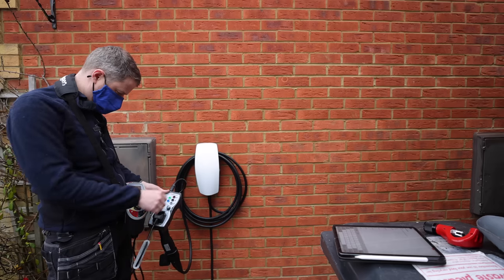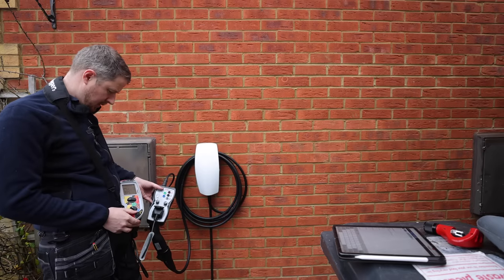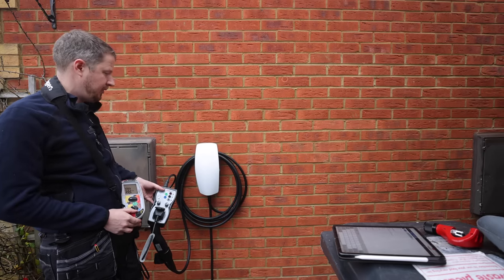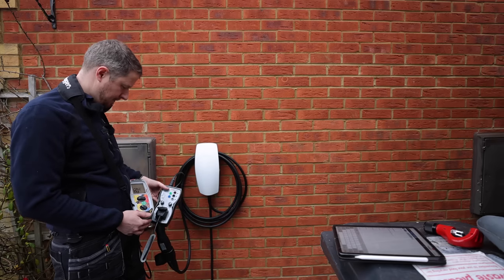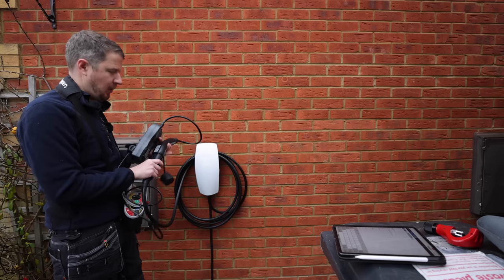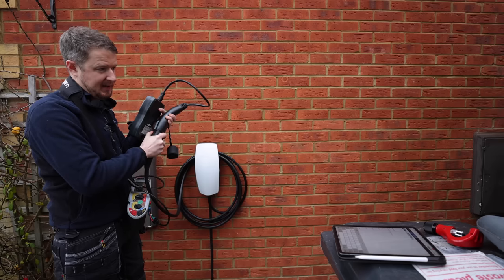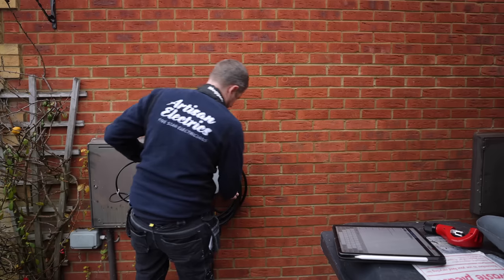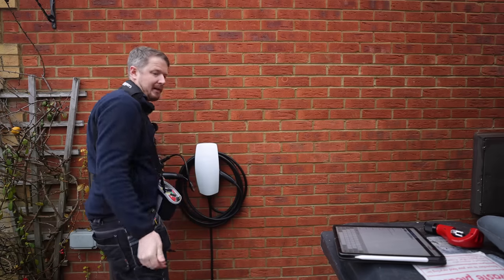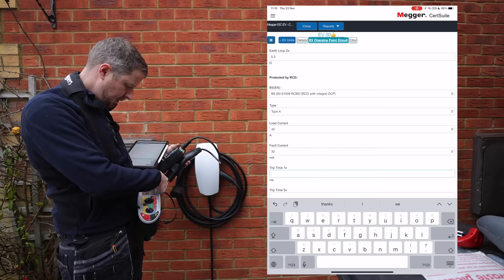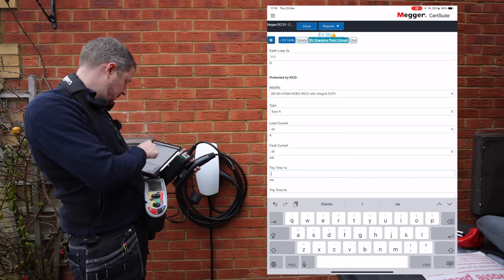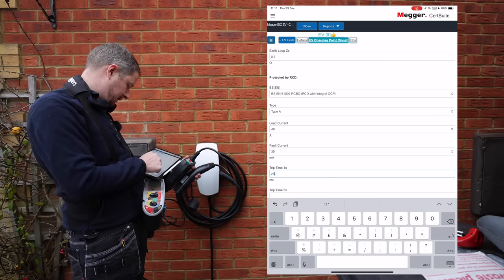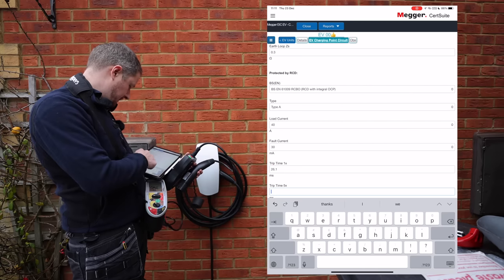So we do the ramp test, we click, and we put 17. It's really nice to be able to input these details, and DC monitor is internal so we can include that. And then we do our one times trip, so just turn it off and then turn it back on again, essentially. We'll put it on auto test. So we've got 26.1. Take this off now, there we go. Now it's doing our five times, we've got 8.38. Here we go, last test, 15.8. That's it. So that's all of our functional and safety tests done, everything works well, and we can record all those readings in our test certificate, which is a lot more information than a lot of your basic test systems and certification softwares have.